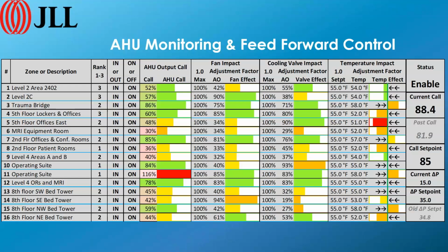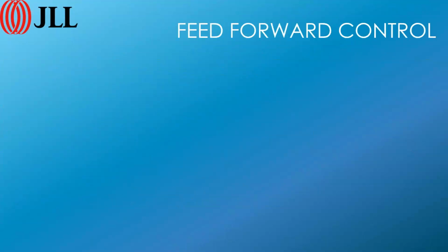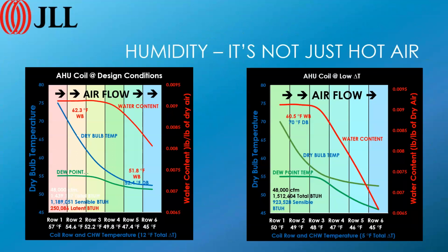Okay. Here's another one. Have you looked at coil efficiency from fouling? With low delta T driving more condensing in the center of the coil and water causing more biofouling in the middle of the coil, have you seen a relationship? Yeah. The low delta T really causes a problem with biofouling in the middle of the coil. It really does, and it is a serious problem.